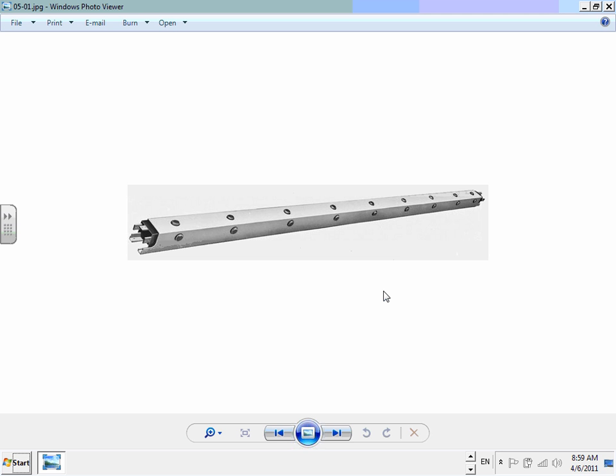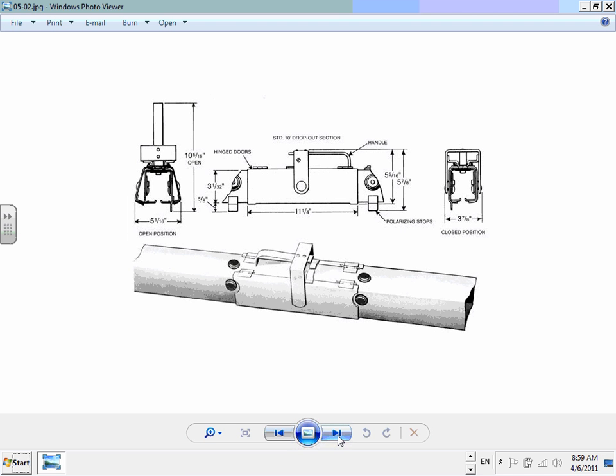The main reason for having a trolley busway is to be able to move the load along a predetermined path. Really, this is the only reason you would use it. Size-wise, I always use the same sizes, and 225 amp is the smallest you can get. In our project we do not have a trolley busway, but it allows you to move the load, like a drill. You move the drill as you move through and work on the machine. So that's really the most important thing.